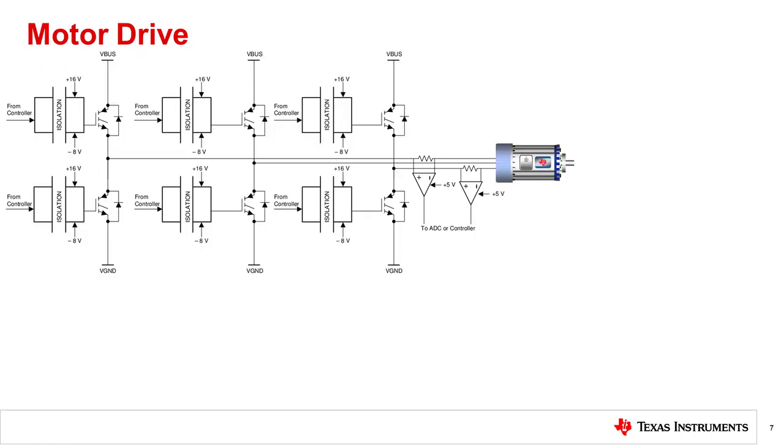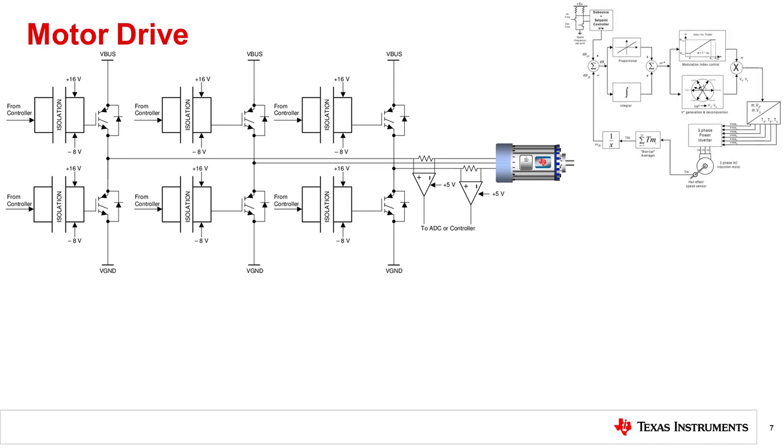Motor drives are inverters, and like solar string inverters, the flow of power and the general DC to AC energy conversion principles are similar. Unlike solar inverters, which must generate high-quality AC power with narrowly defined voltage and frequency range, motor drives are designed to allow variable frequency and sometimes variable voltage. There are numerous motor control schemes and topologies, some vastly more precise and complex than others.